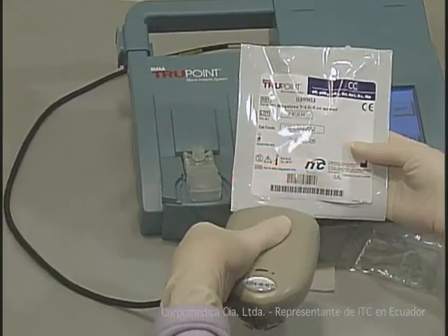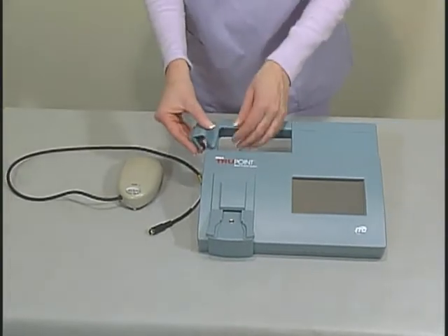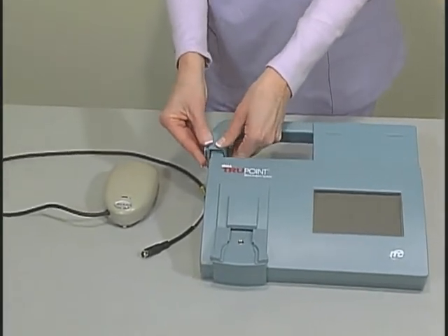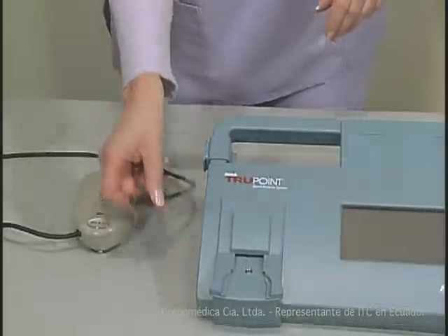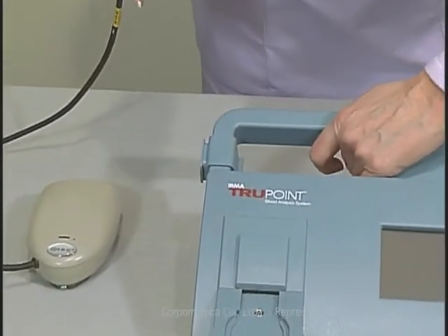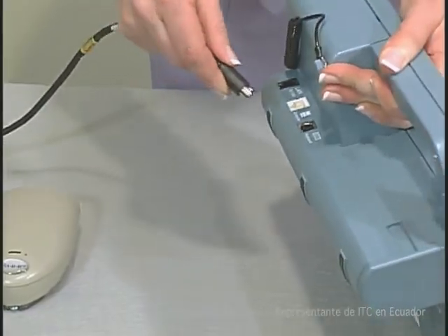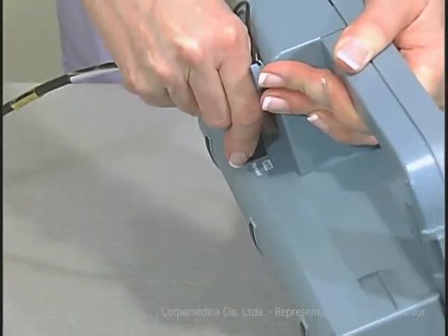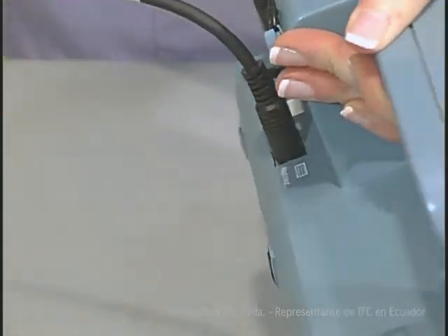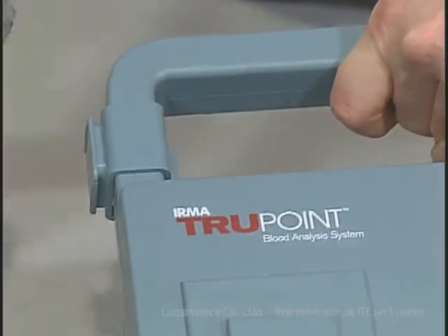A high-performance barcode scanner is available for IRMA TruPoint analyzers. The barcode scanner enhances compliance by supporting positive patient and operator identification. It can also be used to scan QC reference ranges and identify and document cartridge lots and cal codes. The barcode reader is easily attached to the IRMA TruPoint by using the clip mounting.